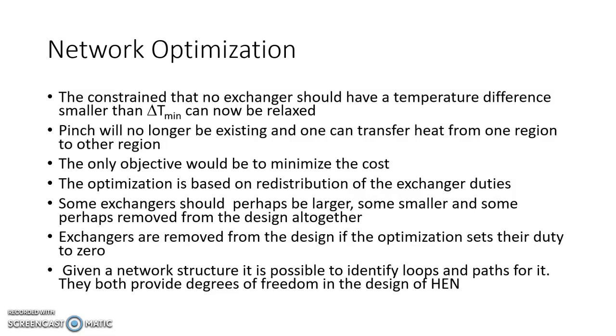Some exchangers should perhaps be larger, some smaller, and some may be removed from the design entirely — all by shifting duties. When an exchanger's duty is set to zero it is eliminated. Removing one exchanger means utility on the other side may increase, but capital cost may go down, so ultimately you have to evaluate the total cost.